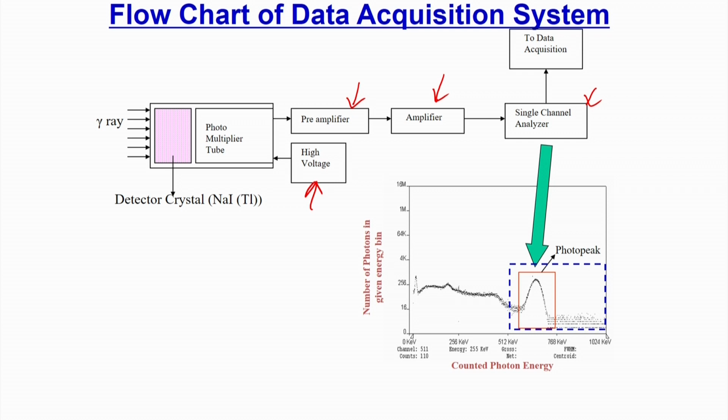It also analyzes what energy the incident photon had, because if the energy of the photons is very high, then the probability of absorption of those photons in the scintillation detector crystal is low, and so the intensity will also be different. So, we calculate the energy of the system, roughly, and we get this kind of a photo peak curve. For each detector, each time, you will get this kind of a curve.